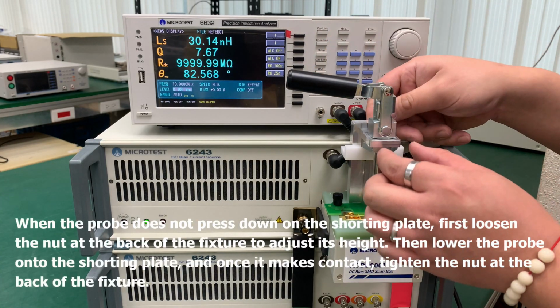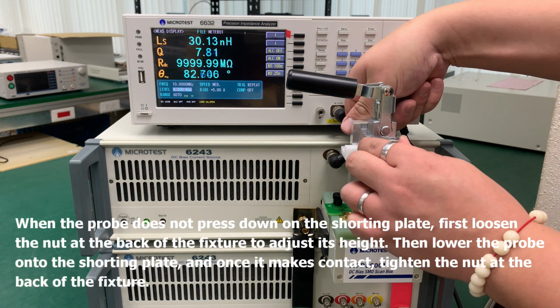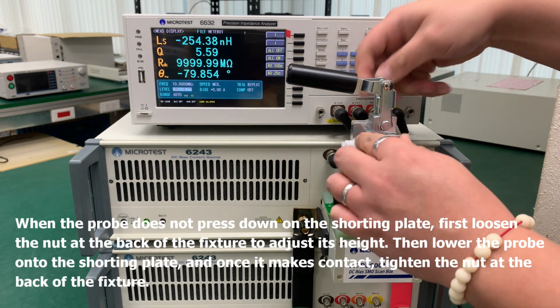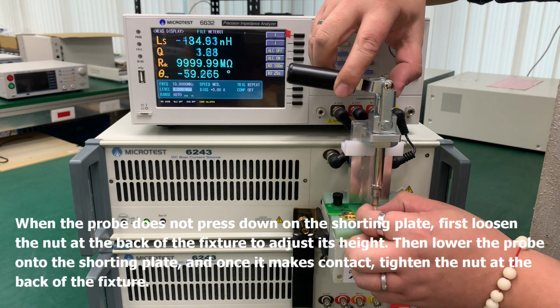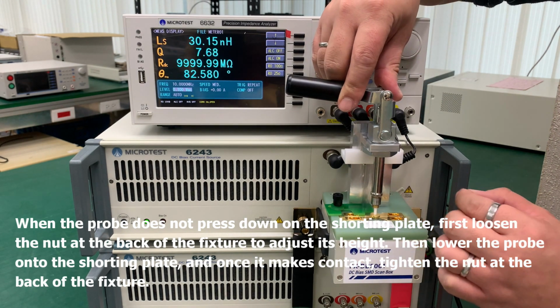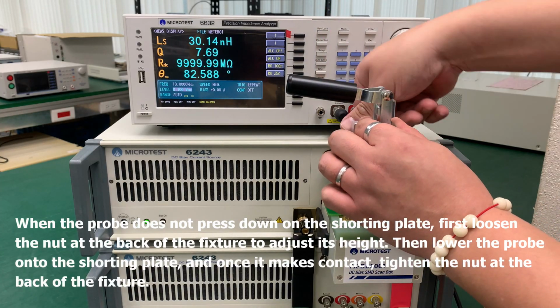When the probe does not press down on the shorting plate, first loosen the nut at the back of the fixture to adjust its height. Then lower the probe onto the shorting plate, and once it makes contact, tighten the nut at the back of the fixture.